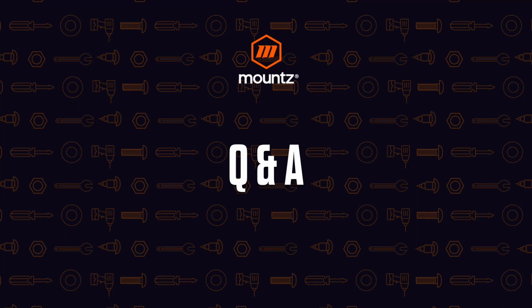Because the last thing you want is to send a tool out for calibration and it comes back as found out of calibration. So you really have no idea at what point did that tool go out of calibration while it was being used. But if you have a way to test that tool on a periodic basis, say it's once a week, once a month, once every 2 weeks, once a shift, that type of thing, you can then begin to track the performance of that tool and make sure that if it is showing signs that it is drifting out of calibration, that it either is adjusted or that tool may be sent to look to see if there's something else that's going on and if it needs any type of repair. So the torque verification process really can help improve the overall quality, because the tools are producing the torque that's needed within their calibrated range.